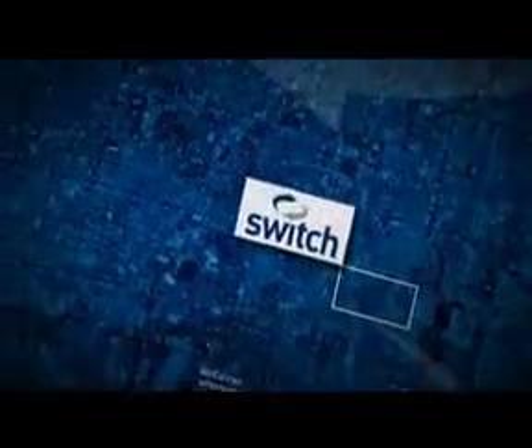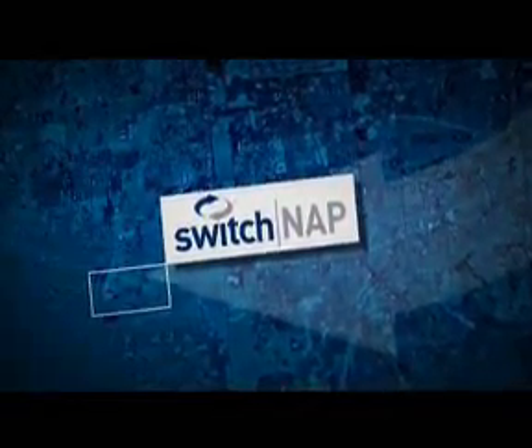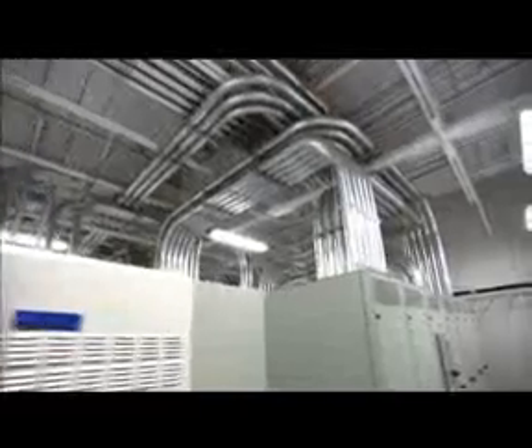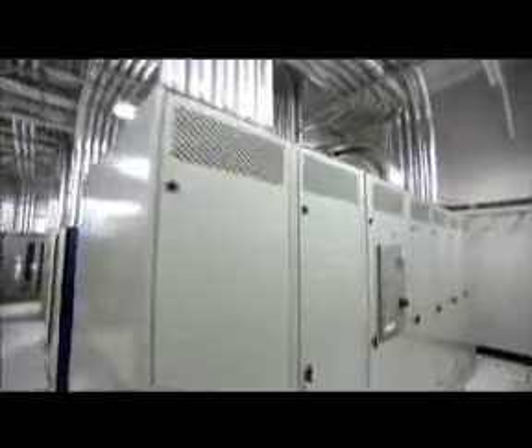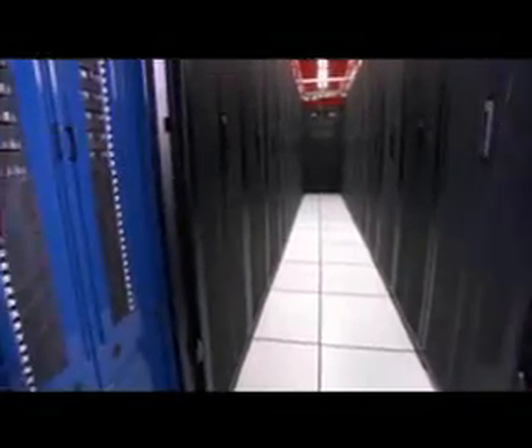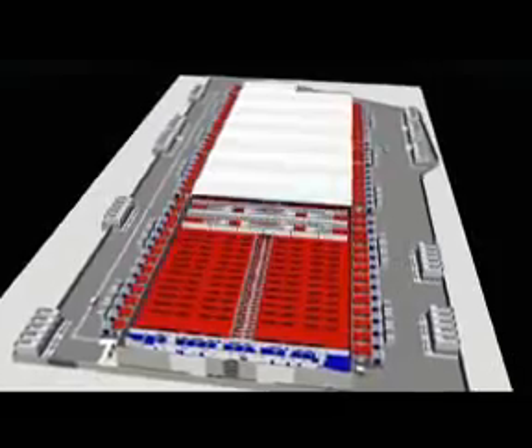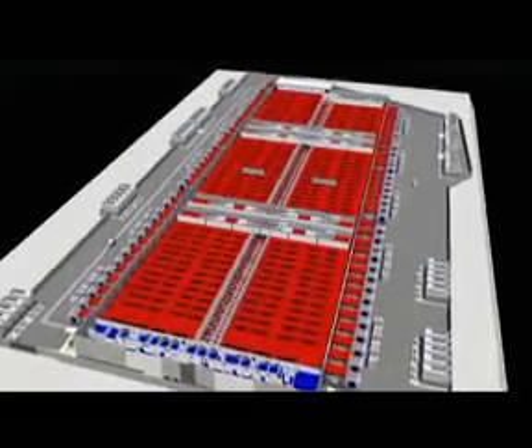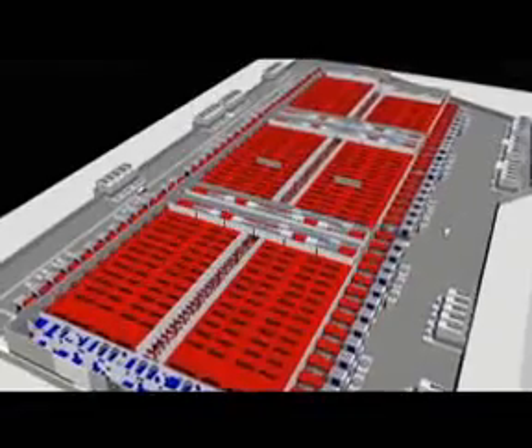Switch owns 6 co-location facilities in Las Vegas, but the SuperNAP, or Network Access Point, is by far the largest. It's the world's highest density data center ever built, and one of the 10 largest single standing facilities in the world. It's got over 100 MVA worth of power delivered to it, 150 MVA worth of power generation sitting on it, designed with system-plus-system critical power distribution infrastructure. The entire building is cut into 6 data center zones, each about 47,000 square feet. It's just massive, 407,000 square feet, which is like 10 football fields under one roof.